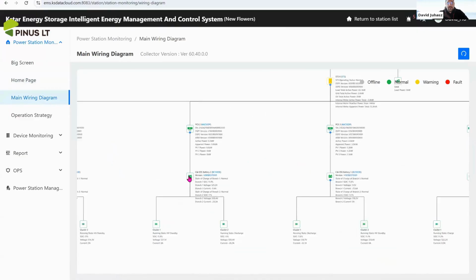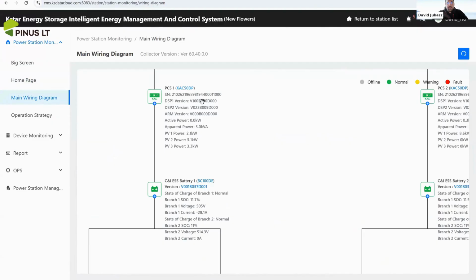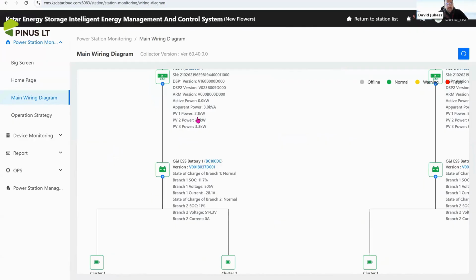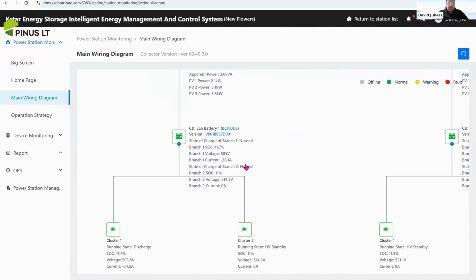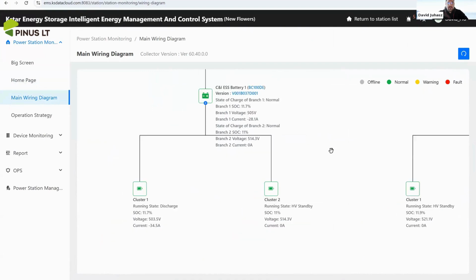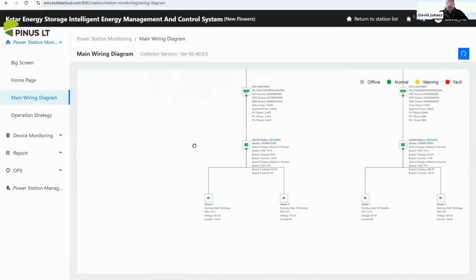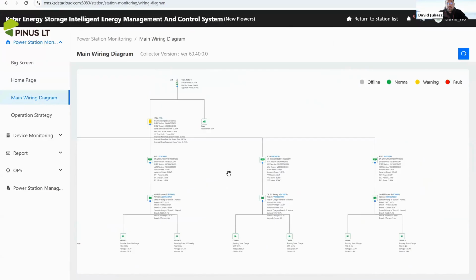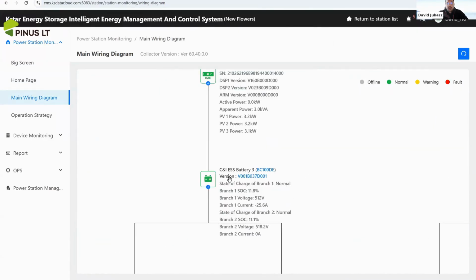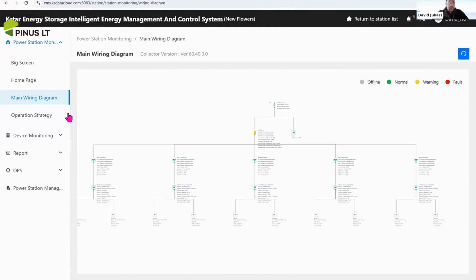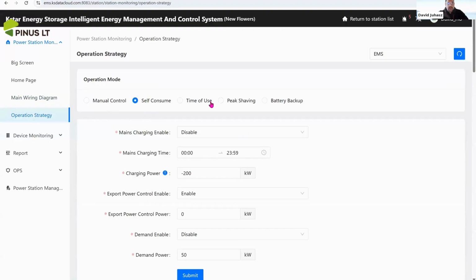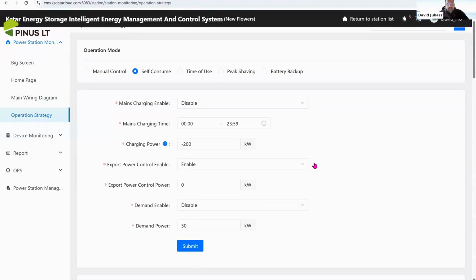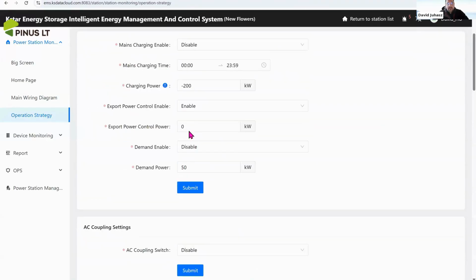Next we can see the main wiring diagram where all of the equipment can be checked about the parameters, the real-time PV production, the SOC levels of the cabinets, and even the clusters of the battery cabinets. So the whole system drawing is visible online as green ones. Next is the operation strategy. We have these 5 operation strategies that I mentioned before. This system is in self-consumption mode, and we can set several things here, which is needed.